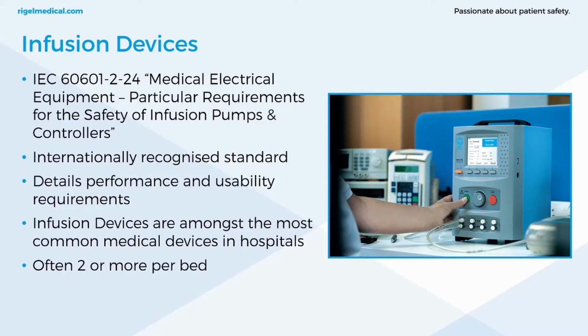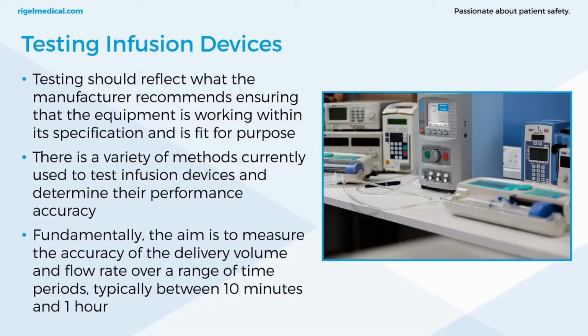Infusion devices are the most common devices in hospitals. They are often 2 or more per bed, and it's crucial that these devices are performing correctly and accurately, and this is what the 60601 standard aims to cover. So testing should reflect what the manufacturer recommends, ensuring that the equipment is working within its specification and is fit for purpose. And so within service manuals you'll have preventative maintenance schedules. This is what you need to follow for regular testing of infusion devices.